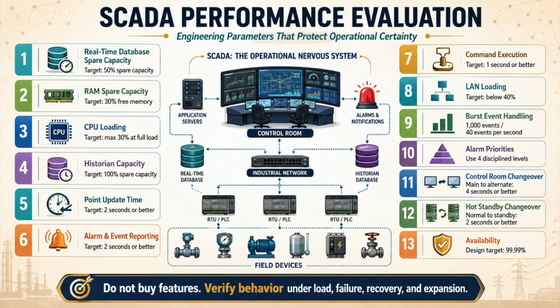The 12th engineering parameter is normal to hot standby changeover, because a 2-second or better transfer proves whether standby is actually hot, synchronized, and operationally credible. A standby system that only exists in diagrams is not redundancy. It is a design assumption waiting to fail. True hot standby must preserve process data, alarm state, historian continuity, communication sessions, command status, operator visibility, and client reconnection under peak load. Therefore, the primary server must be failed during realistic operating conditions, not during an empty demonstration, and standby takeover must be verified without loss of critical state.